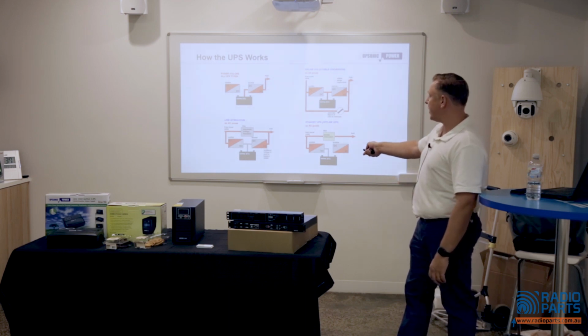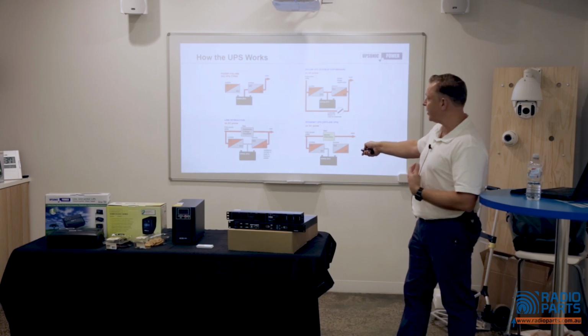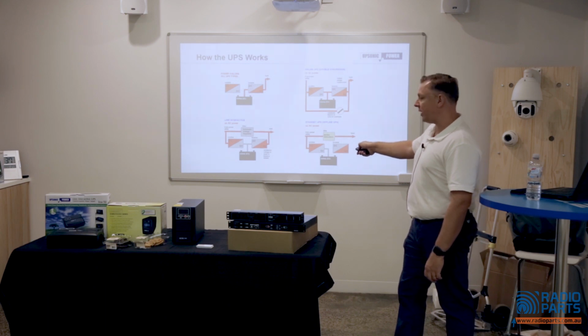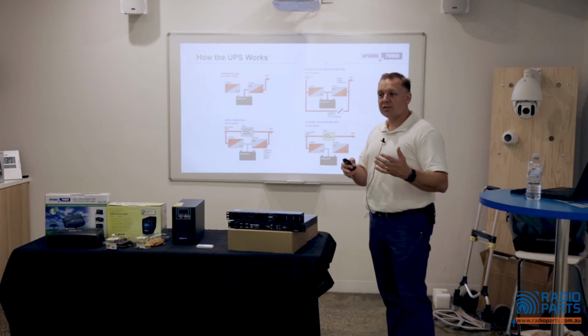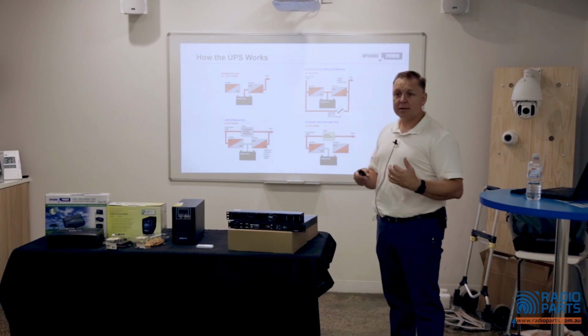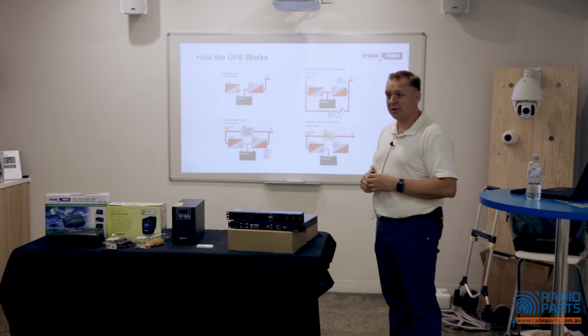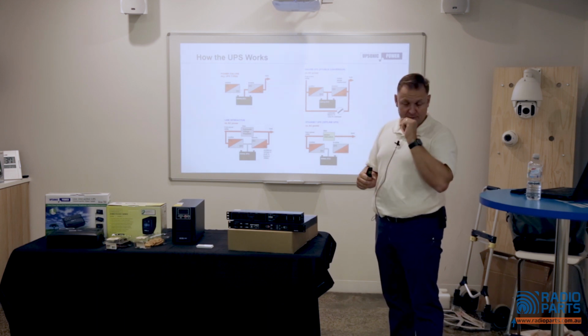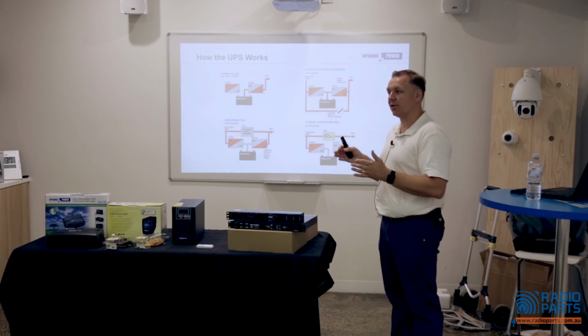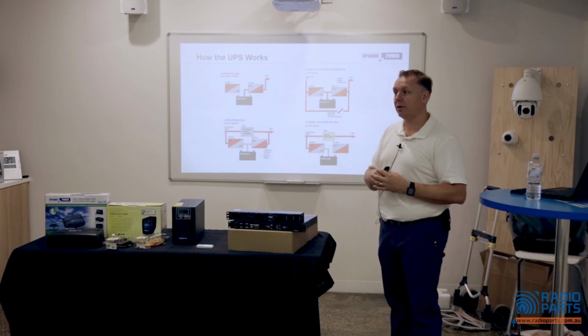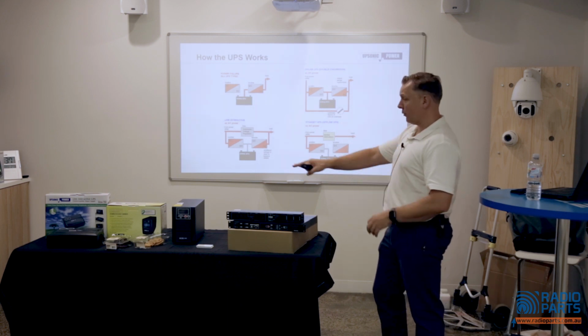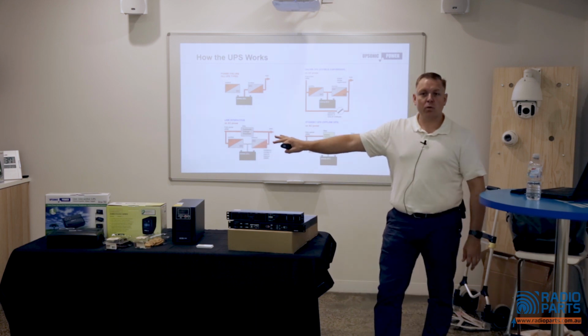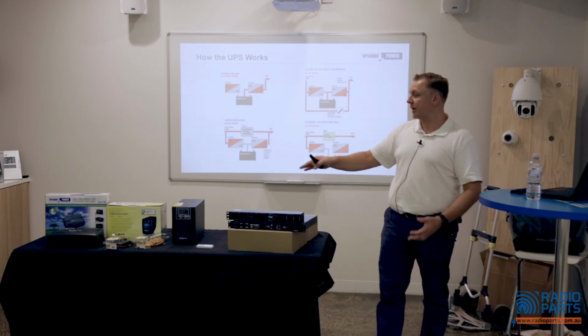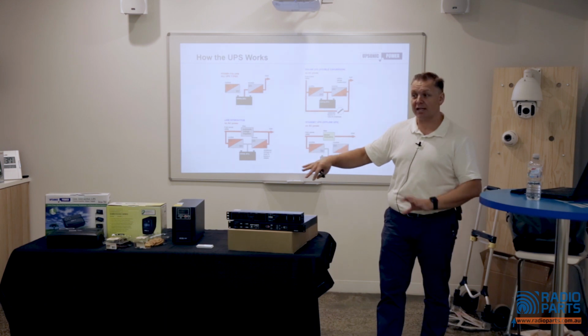When we get to our line interactive, so with Upsonic, our ESAT range, they have this voltage regulating filter. The biggest difference is that the rectifier is a little bit bigger. It is able to supply the DC bus within the UPS to some extent. And the advantage of that is it can filter the supply to a higher extent. With a standby unit, when the supply gets out of spec to a certain point, it'll switch on to batteries, and that's all it can do.